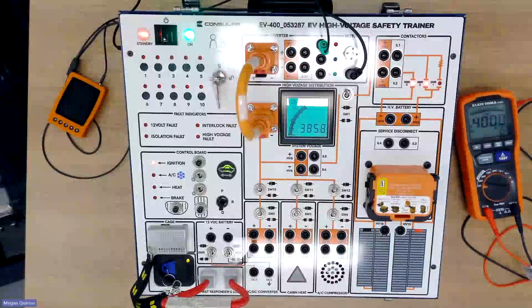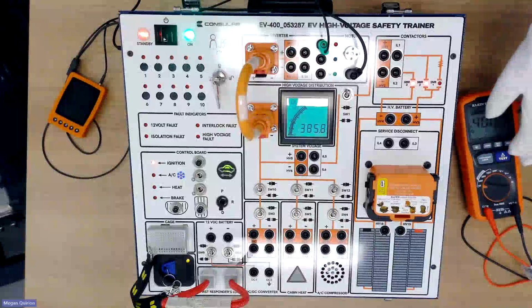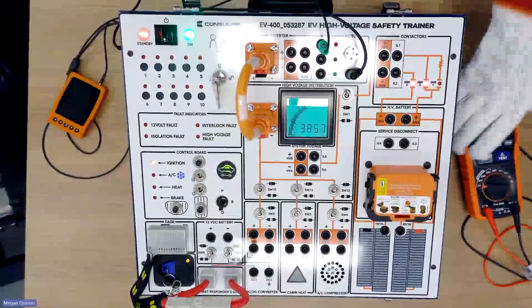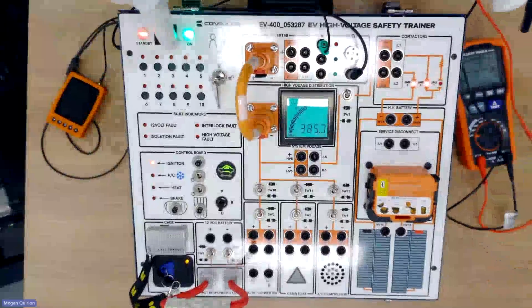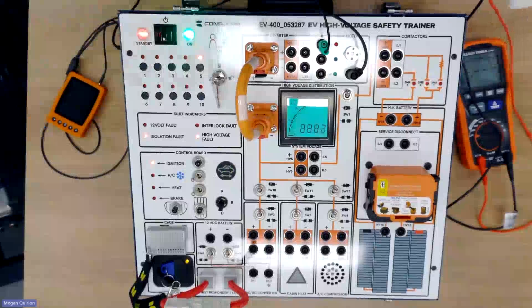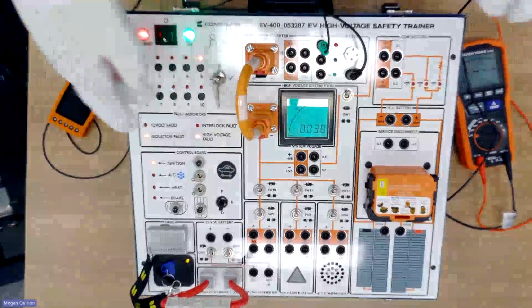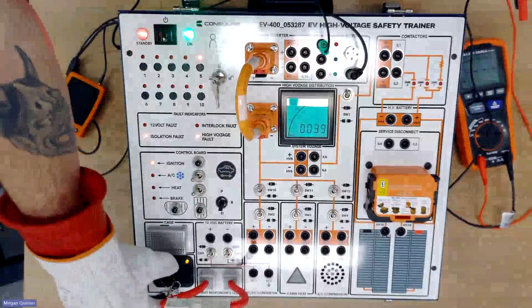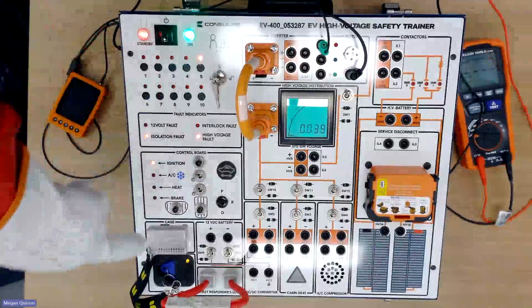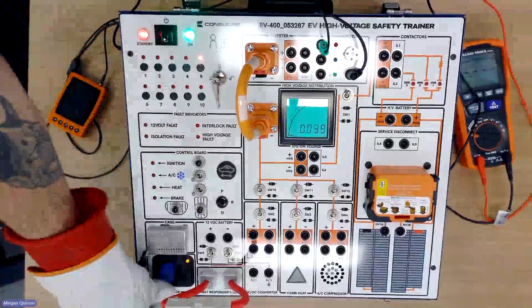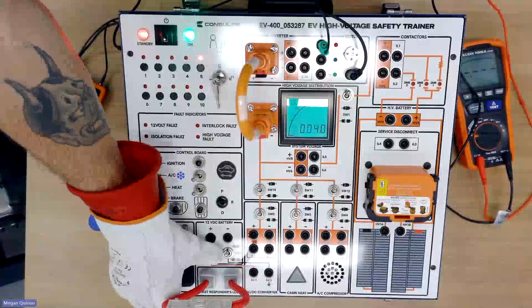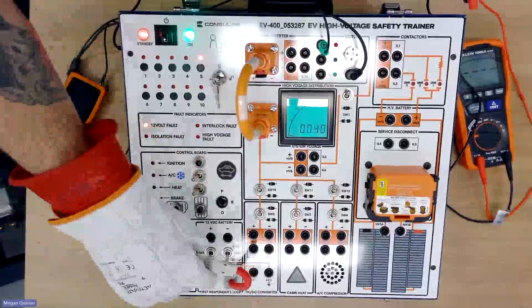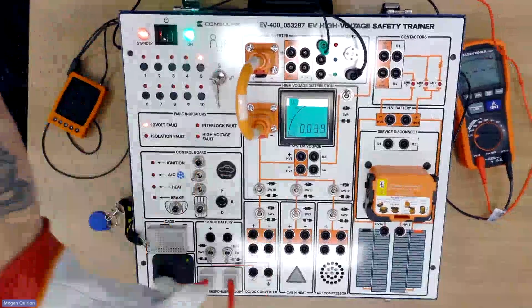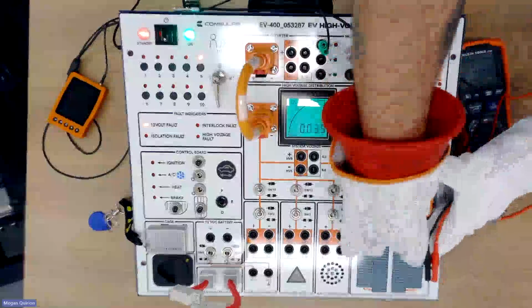Okay, so here we are. We're now going to test to show what it looks like when we have an isolation fault using the 400. So what he's going to do is set a fault within this unit, and we're going to go through a power down. Notice the contactors have turned off, the unit's down. Now we're going to go through the procedure to actually test it, looking for a fault using our isolation tester. He's going to disconnect all the required components, and disconnect the 12-volt battery.